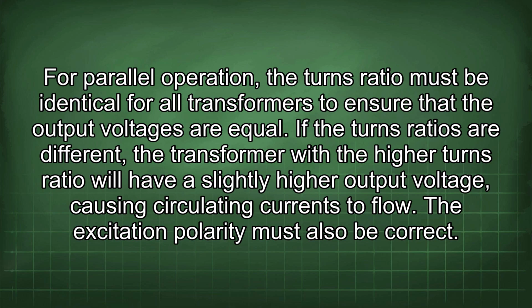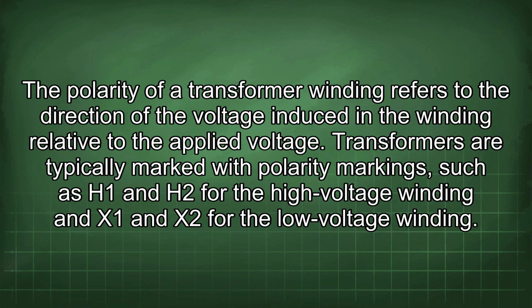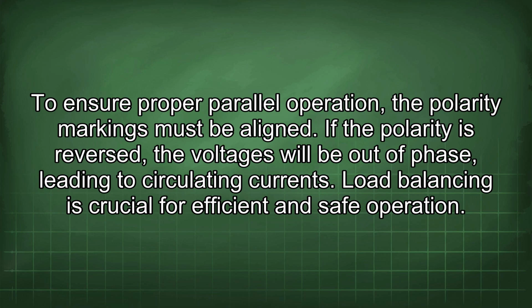For parallel operation, the turns ratio must be identical for all transformers to ensure that the output voltages are equal. If the turns ratios are different, the transformer with the higher turns ratio will have a slightly higher output voltage, causing circulating currents to flow. The excitation polarity must also be correct. The polarity of a transformer winding refers to the direction of the voltage induced in the winding relative to the applied voltage. Transformers are typically marked with polarity markings such as H1 and H2 for the high voltage winding and X1 and X2 for the low voltage winding. To ensure proper parallel operation, the polarity markings must be aligned.